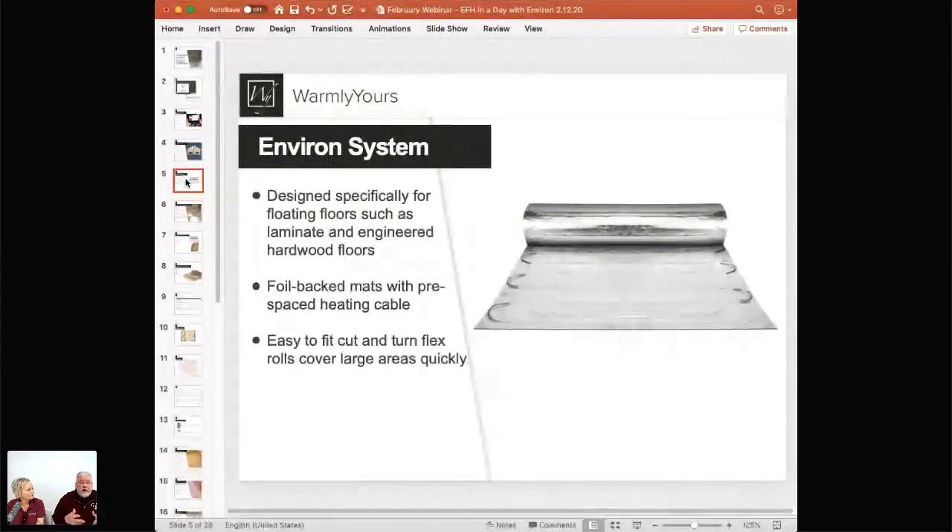It's heating wire embedded in foil. The foil helps spread the heat out, and it lets you cut and turn because you simply pull the loop up a little bit to cut that section and turn it. It's very flexible and can adapt to the room. It's good for filling rooms that aren't exactly square. It's used for any floating wood system. For luxury vinyl tile — LVT, SPC core, and derivatives — that is a system that would not be used with Environ, because LVT is typically embedded in self-leveling.